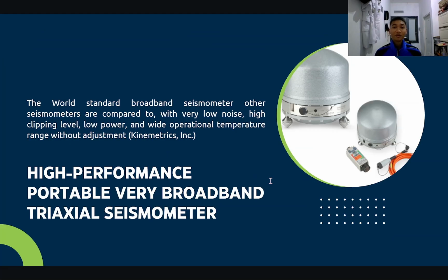Let's move on to the first device, the Streckeisen STS 2.5. This device is a high-performance, portable, very broadband triaxial seismometer. In the world of seismology, the STS 2.5 is recognized as the world standard, against which other seismometers are often compared. Its advantages include very low noise levels, high clipping levels, low power consumption, and the ability to operate over a wide temperature range without the need for readjustment.